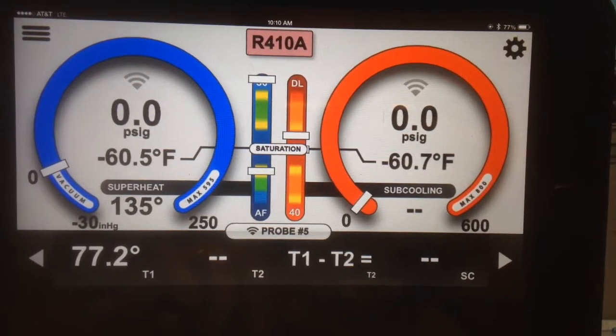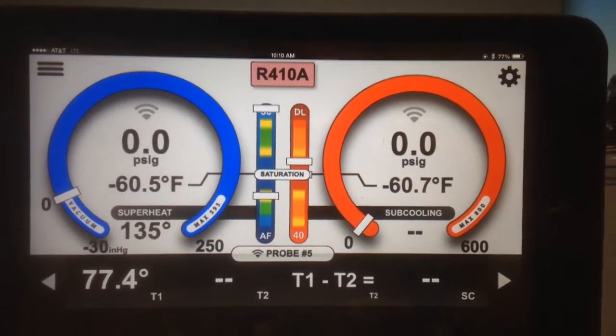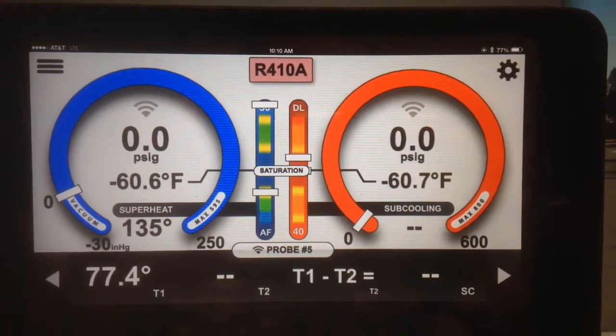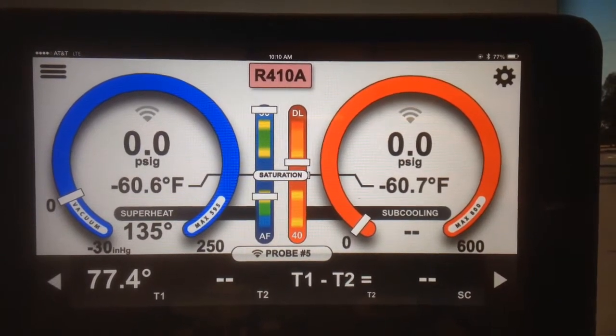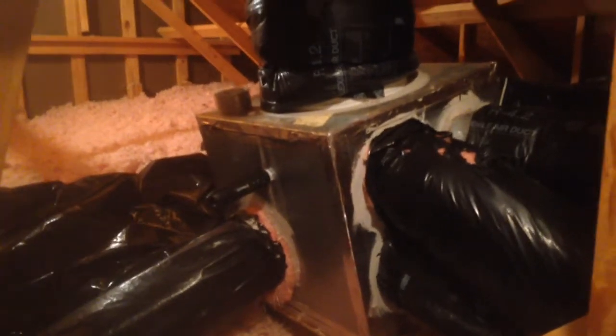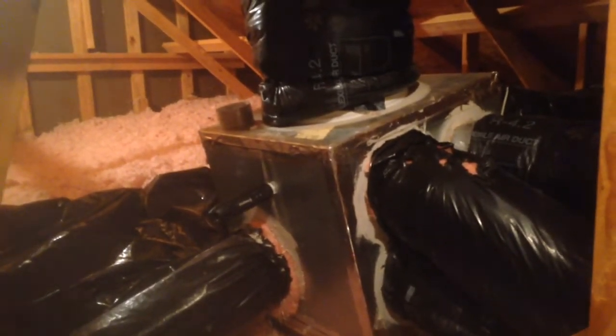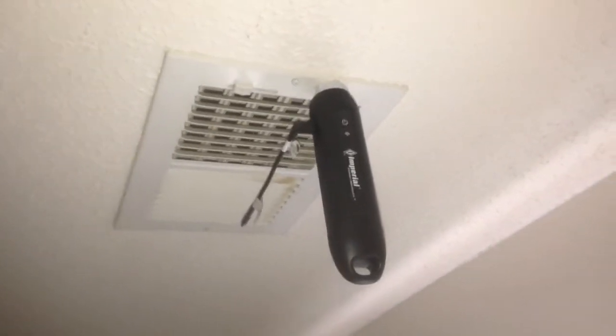There you go. So just for fun, we're going to leave this probe in the repeater so that we can confirm connectivity. And we're going to go ahead and put the temperature probes in the ducting in my attic. The return air probe is into the return plenum on this side of the unit. And the supply air probe is over here in this distribution box. And then we're going to take the repeater probe and, just for fun, show it over by one of the supply registers on the second floor. There you have it. The magnets on the repeater probe allow me to stick it to the register.